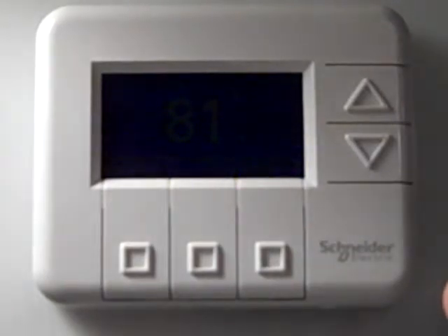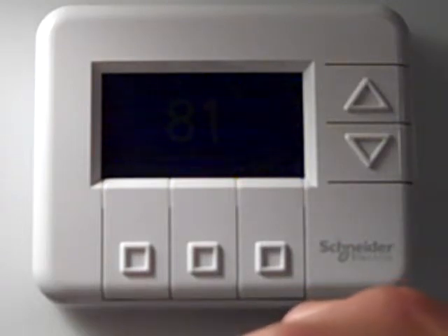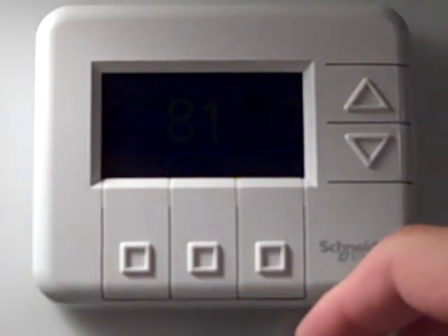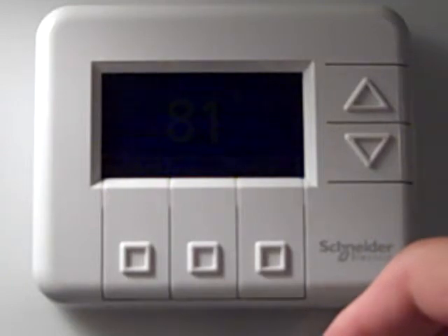This little snippet, I just want to cover a troubleshooting procedure and then use the operating mode to verify, in fact, that we've got the thermostat set up properly. In the case of an issue where we had a thermostat that's been communicating and then it's not communicating, we may have swapped out that thermostat, or perhaps we have a slave thermostat that was communicating that's no longer communicating after maybe we swapped out a thermostat.